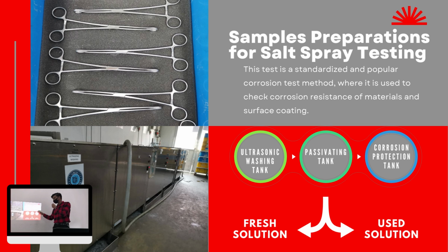Okay, and then for the passivating tank, basically it creates a coating on the instrument to prevent corrosion, and the corrosion protection tank provides protection for the coating. Okay, and this sample will be broken into two types, which are fresh solution and used solution. Basically, used solution is the used solution of the ultrasonic tank. You will go through different instruments. There are different instruments that go through all this. Basically, the used one. So when you're testing it, you know that it's a used solution.